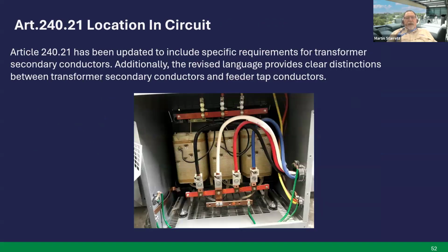Next slide. Article 240.21, location in circuit. Article 240.21 has been updated to include specific requirements for transformer secondary conductors. And as we learned on Monday, we have a new definition for transformer secondary conductors. The reason the definition was added was pretty much for this article here. Additionally, the revised language provides clear distinctions between transformer secondary conductors and feeder tap conductors. Next slide.